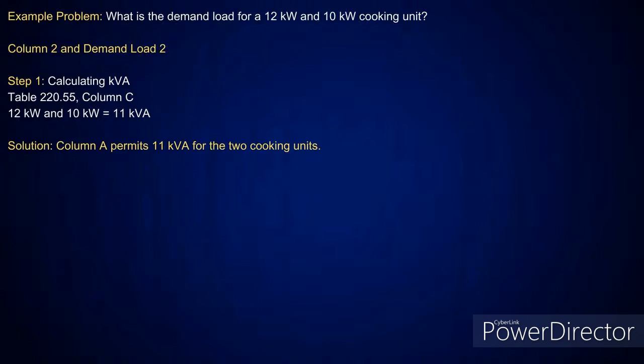All right, now let's take a look at this. We're going to go through quite a few calculations dealing with our cooking equipment, folks. This first one, we have a 12 kW and a 10 kW. If you look at column C, this is probably the one you're going to use most, where you're not over 12. Once I get over 12, then we're going to do some other things with the notes. But columns 1, 2, and 3 are very specific.